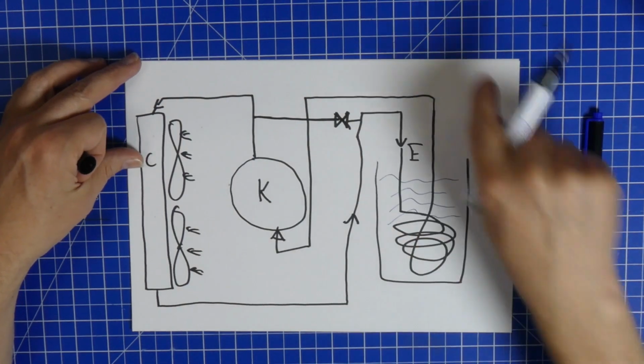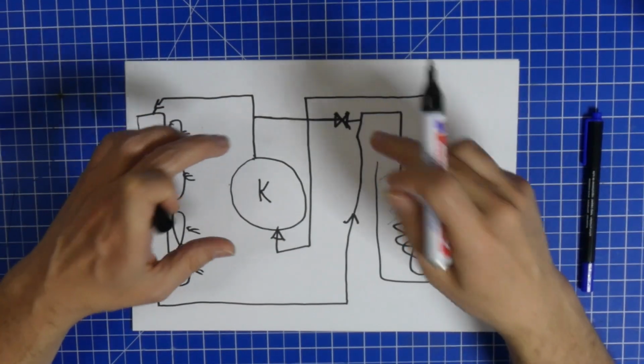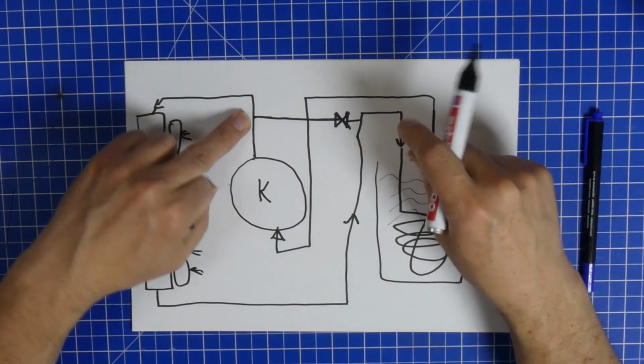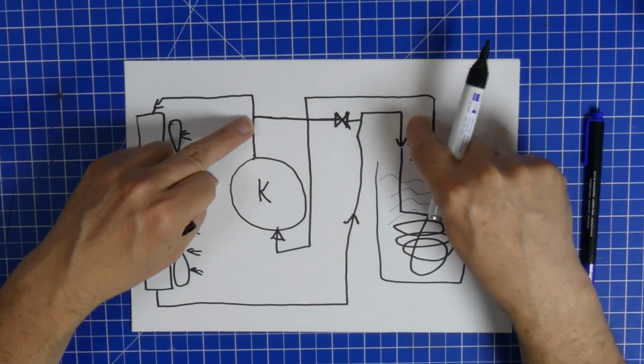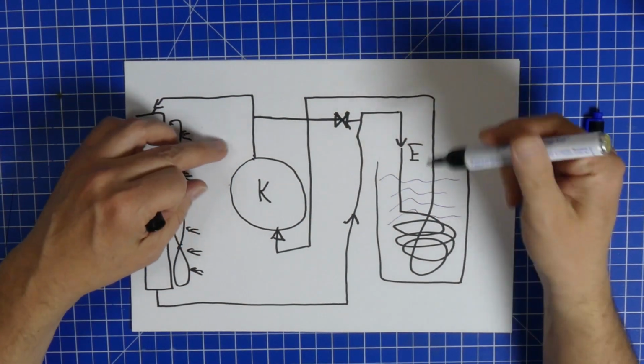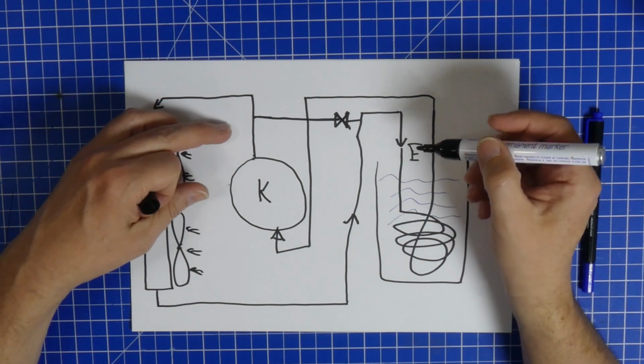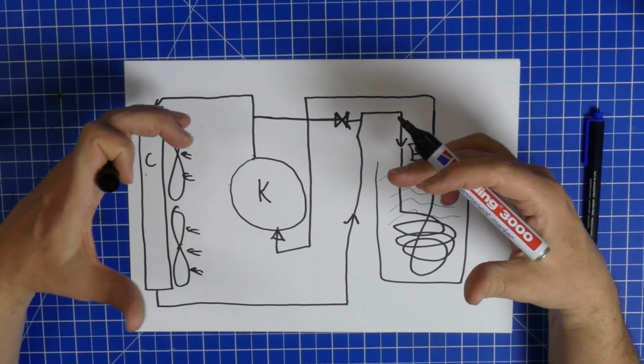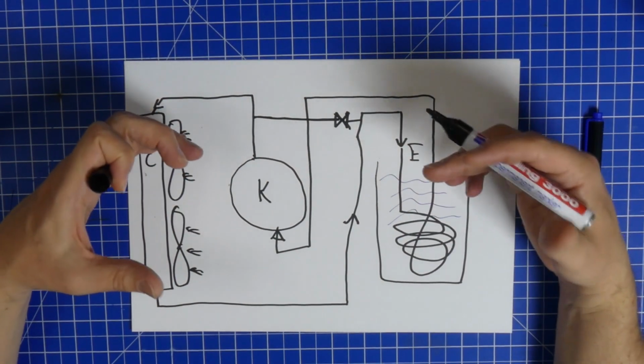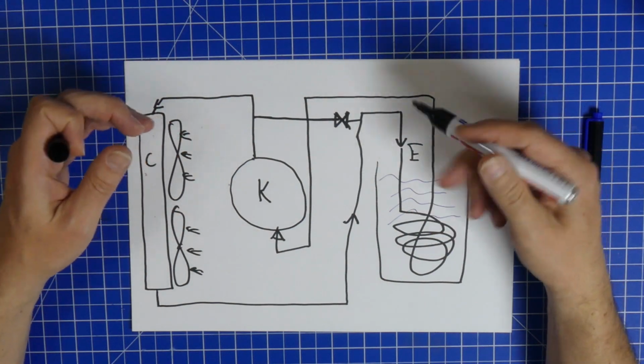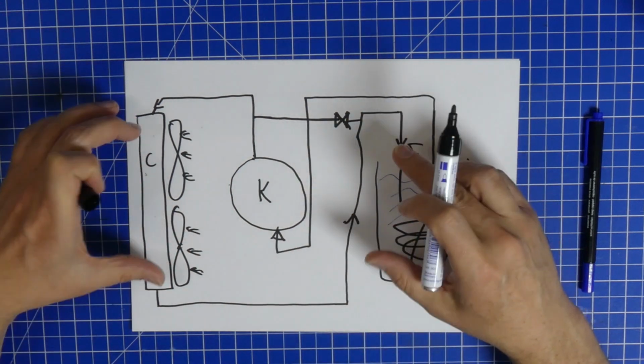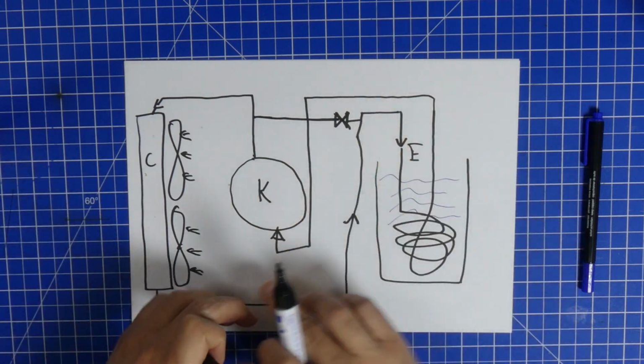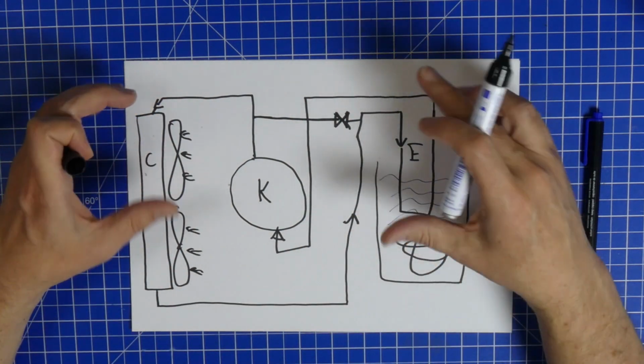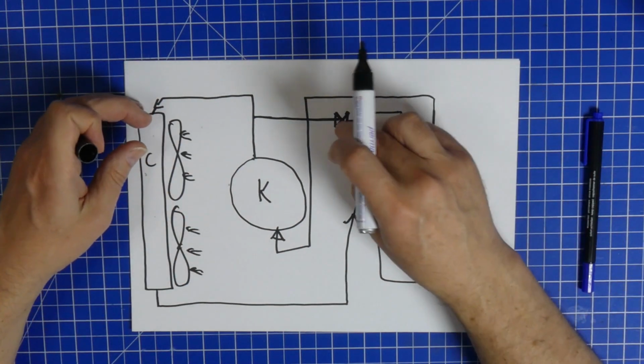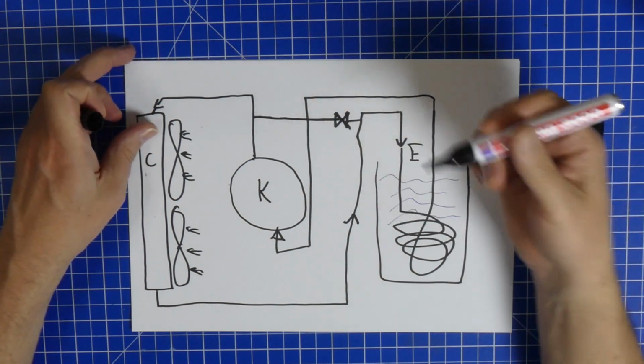So in normal state, when it's operating, this valve is closed and we have a real AC. In a second state, this valve here is opened and hot gas from the compressor can get straight into the evaporator. When this happens, the whole system goes into a sort of stalemate. It doesn't really cool anymore, or it loses a lot of its cooling power, because sure, you still have some gas going this way, and you have some of it going through the condenser, turning into liquid and evaporating in the evaporator. But turning this valve on and off is like turning the compressor on and off.